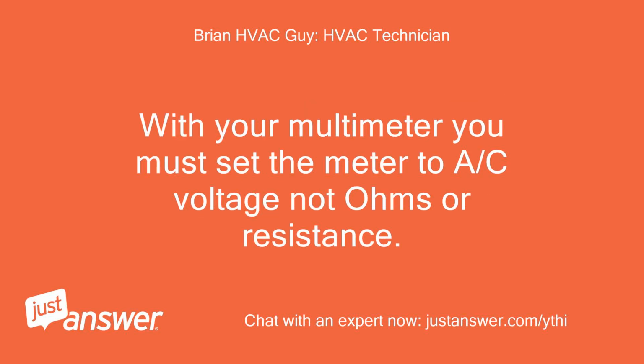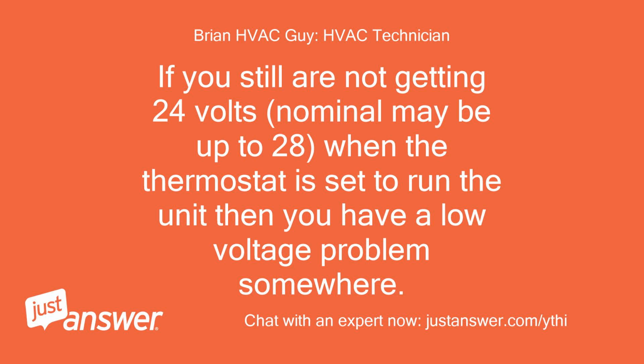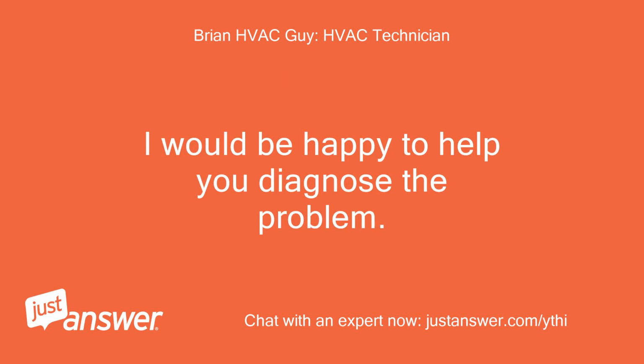With your multimeter you must set the meter to AC voltage, not ohms or resistance. If you still are not getting 24 volts, nominal may be up to 28, when the thermostat is set to run the unit, then you have a low voltage problem somewhere. I would be happy to help you diagnose the problem.